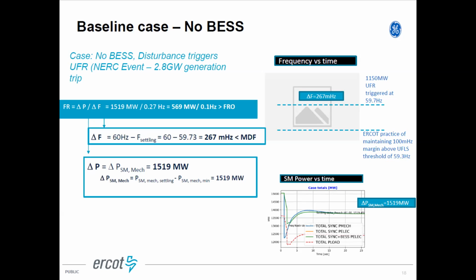I really wish that curve had come up. But anyway, so you see this red curve on the bottom, that's the load, and you see that vertical drop - that's where the discrete load response kicks in. That's about 1150 megawatts of load response to that frequency. And take my word for it that the frequency behaved okay.